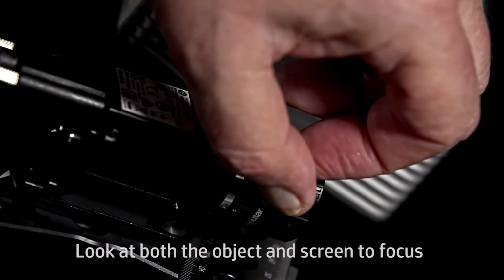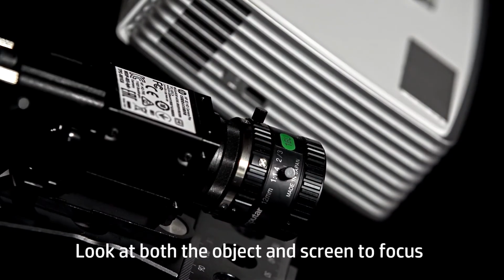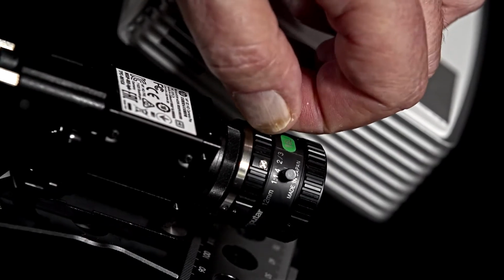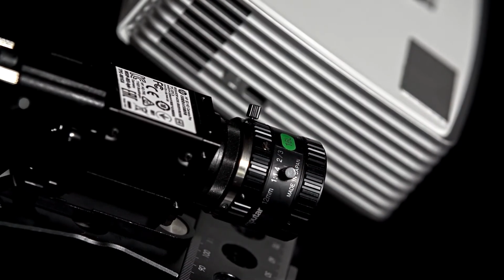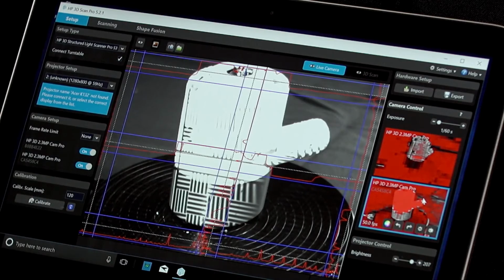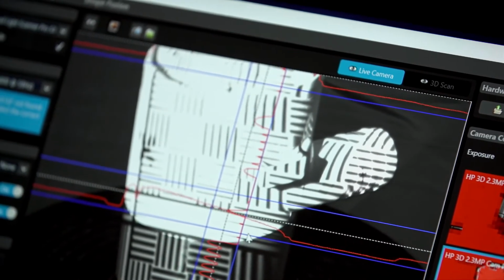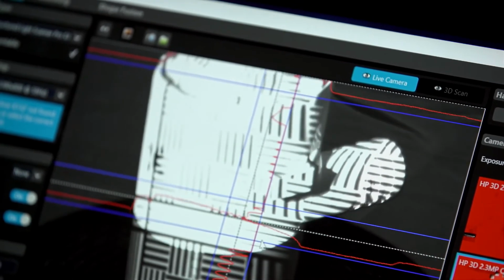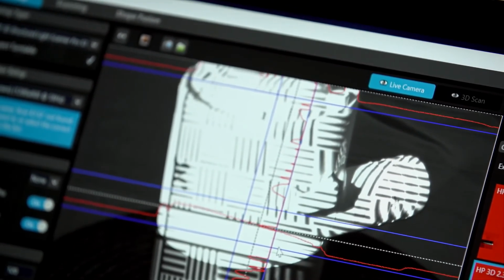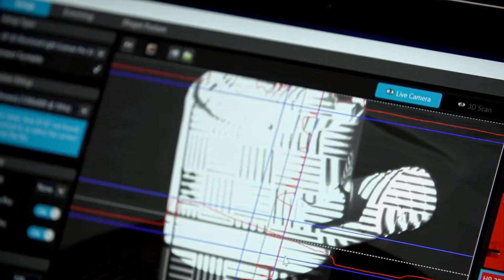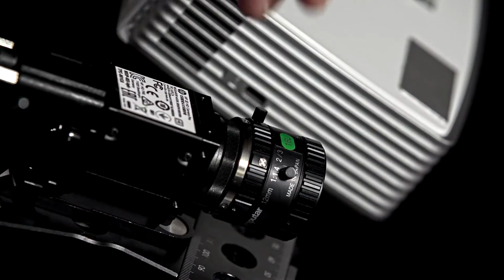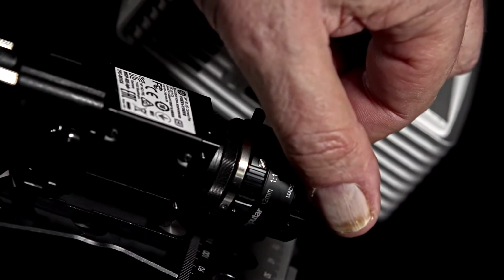This process can be made easier by initially setting the camera aperture open too much using the back ring of the lens so that the image is very bright, and then zoom in on the computer screen. This will make the image on the screen much more sensitive to changes in the camera focus and make it far easier to focus the scanner correctly. Once you have got focus sharp, lock the front focus ring on the camera lens. Click on the Auto Adjust Eye button in the computer software to zoom the image back out again, and then move on to setting the aperture.